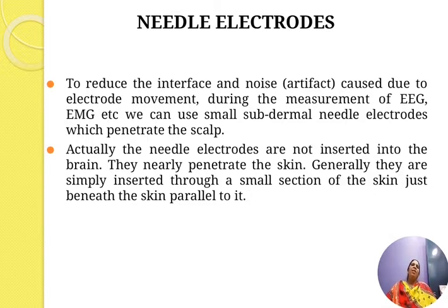Okay. We have other types of electrodes called needle electrodes. To reduce the noise and interference artifacts caused by movement during the measurement of EEG and EMG, we use small subdermal needle electrodes which penetrate the skin. Actually, the needle electrodes are not inserted into the brain. They nearly penetrate the skin. Generally, they are simply inserted just beneath the skin, parallel to it. Okay.